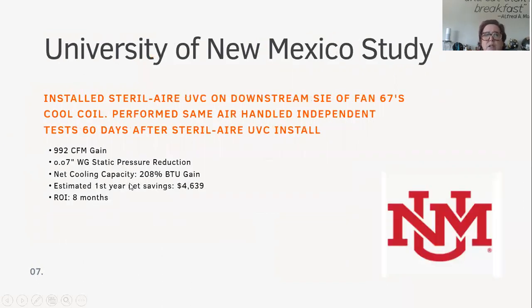In the University of New Mexico study, they installed Steril-Aire UVC on the downstream side of their air handling unit. They performed independent tests on the same air handler 60 days after installation. They were able to document a 992 CFM gain, a 0.07 WG static pressure reduction, and a net cooling capacity increase of 208% BTU gain. They calculated that in this one area they had a 1-year net savings of $4,639. That was an ROI for installing this equipment of 8 months, which was extremely satisfactory and very exciting for them.